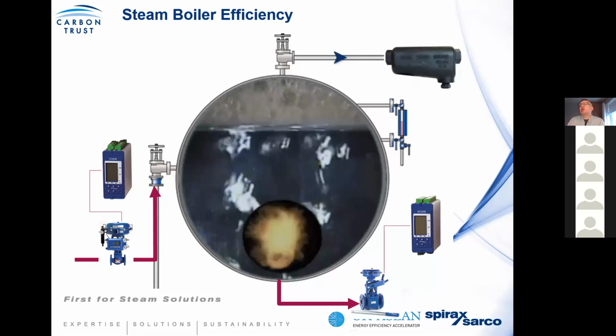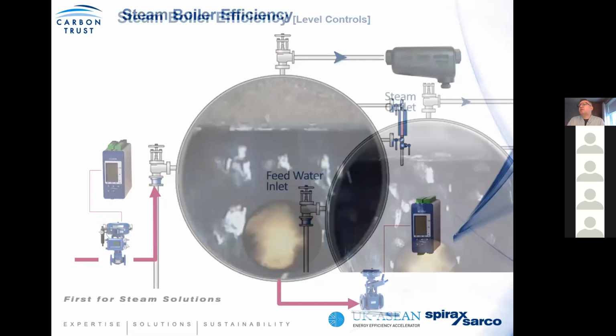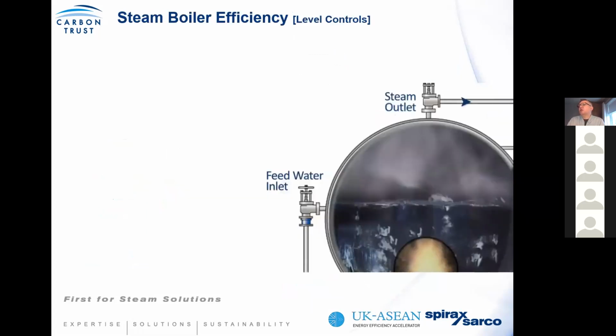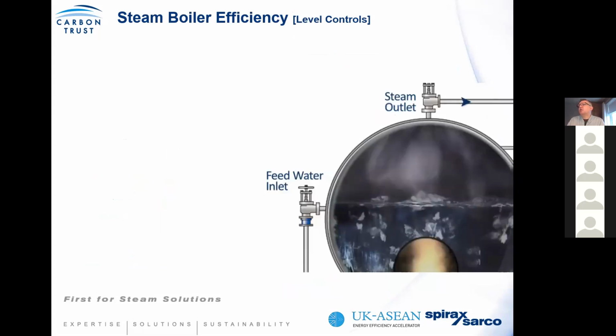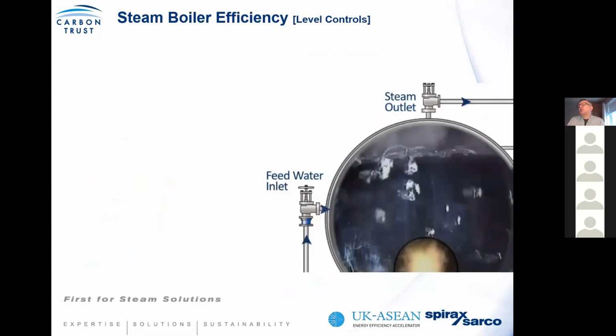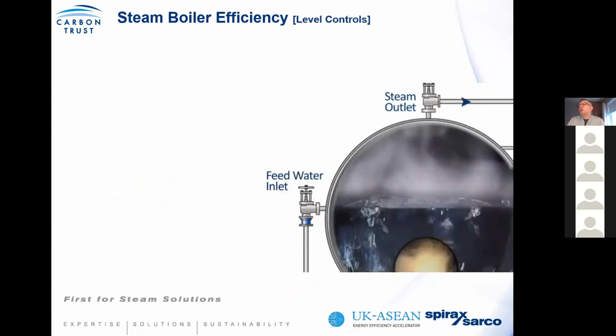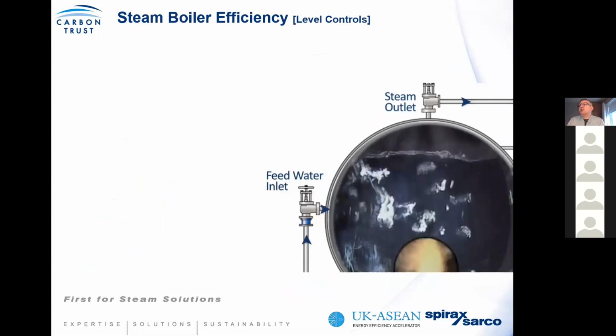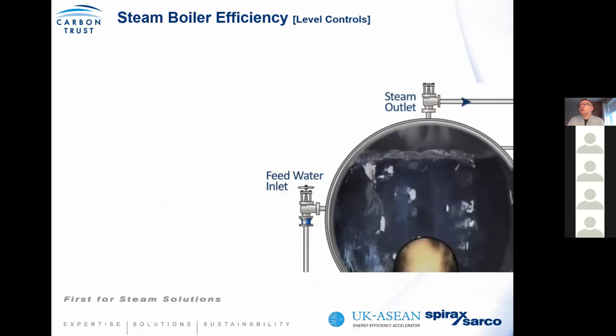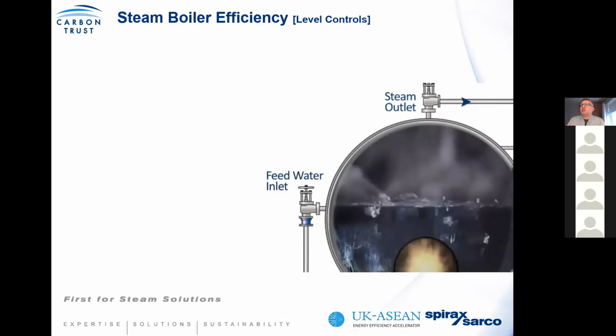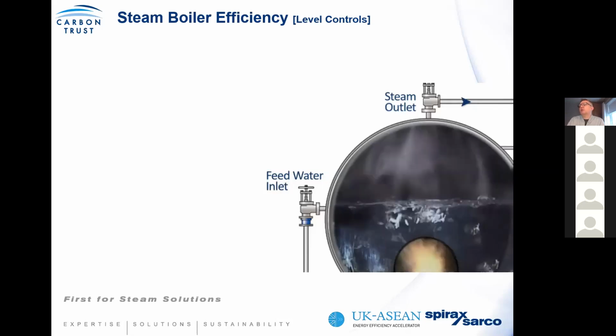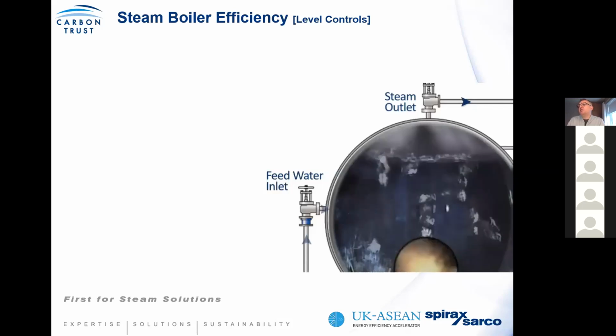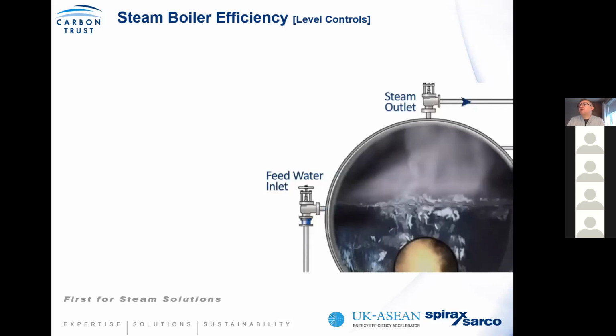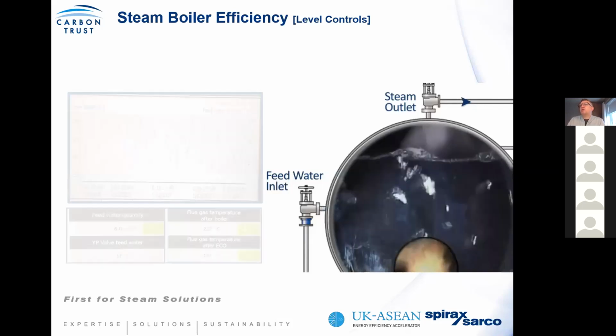Again, we talked about the separation because we want to remove this entrained moisture on generation. Now, when we look at your standard on-off control, what you will see is that as you start adding in water, you're effectively creating a different working level within the boiler. The problem is that as the water level changes, the disengaging space changes, which is the surface water level. And where you have high velocity steam extract, you end up dragging water out of the system. And again, what we're finding is that up to 5% efficiency gain can be achieved where you have effective modulation control. So understand your system.